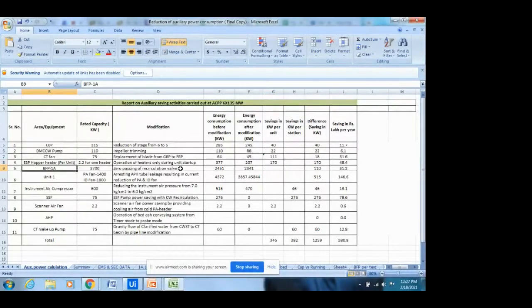In BFP, there was a passing in the recirculation valve. We have rectified it. Leakage in APH tubes in the boiler, there also we have saved energy. In the instrument air compressor, we have reduced the pressure. After analyzing the process, we saw the recirculation line, and instead of running the pumps for SSF operation, we have saved a lot of energy there also. In our scanner fans in the boiler, saving is also possible by providing a cooling air line from the PA duct itself. Then in APH, timer mode operation was there earlier, but after fitting the probes, we could run the APH system in probe mode, and there is also a saving of energy.